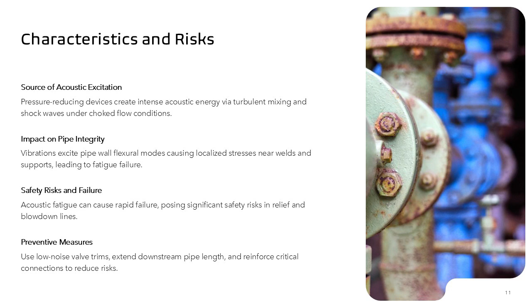These stresses concentrate at circumferential discontinuities like small bore connections, welded tees, and supports, making them highly susceptible to fatigue failure. Acoustic fatigue failures can occur rapidly, sometimes within hours of operation, posing significant safety risks. Preventive strategies include using low-noise valve trims, increasing downstream pipe length for attenuation, and reinforcing vulnerable connections. Acoustic excitation is a critical consideration for safety-related systems such as relief and blowdown lines, where failure consequences are severe.